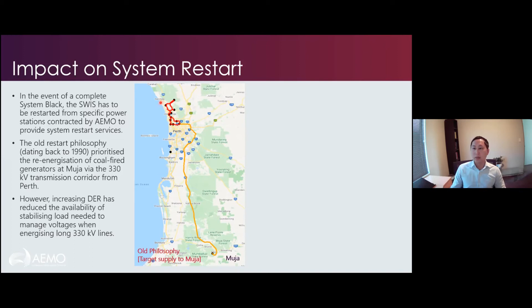Back then we needed that because we didn't have much gas. Since the 90s we've brought on a lot more gas and generation, but in the past we needed all that coal generation to supply load to the SWIS. Now, increasing DER has reduced the availability of stabilising load in these areas. We had a system black event in the middle of the day and tried this approach, but couldn't get enough load to energise the line, since you need stabilising load to energise it and keep the generators stable. We just didn't have enough load in some of these North Metro areas.